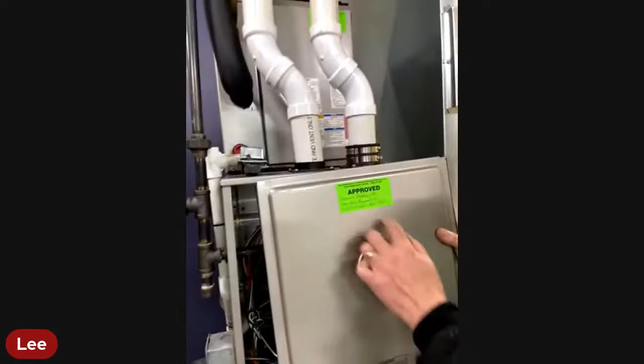A lot of times too, if you call somebody and talk to them, they'll ask if you've tried restarting or rebooting your furnace. So shut that power off, wait 5 seconds, turn the power back on, and listen for those cycles. A lot of times you can look in and see this. Normally this cover is on, but sometimes there's a sight glass so you don't have to pull the cover off.